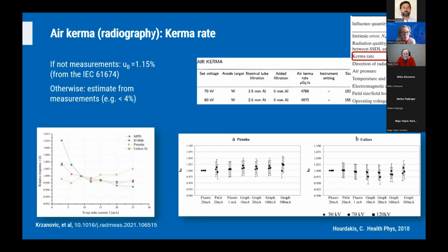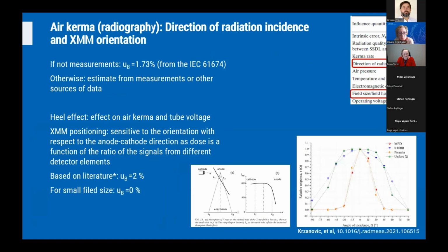Kerma rate is also another parameter to be considered as a contributor to the overall uncertainty budget. And there are different sources that can be used to assess the kerma rate. In principle, according to the IEC standards, the uncertainty would be approximately 1%. From measurements published in the peer-reviewed literature, the uncertainty attributed to the kerma rate should be less than 4%, but according to the few published papers that looked at this property, this uncertainty in reality is even less and almost negligible.